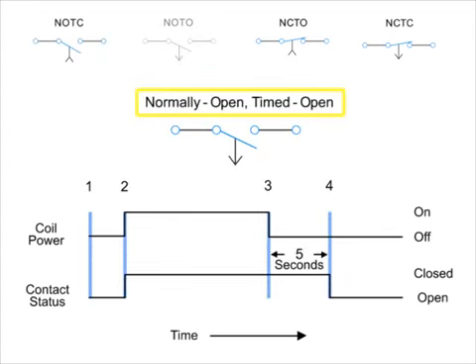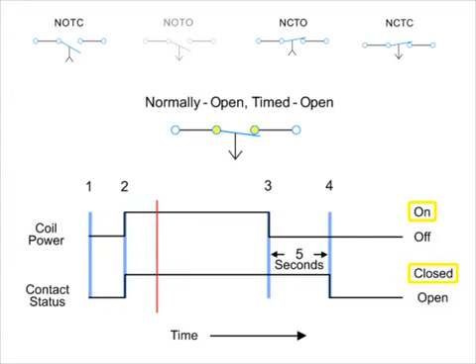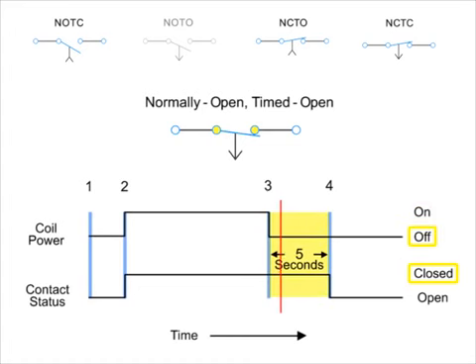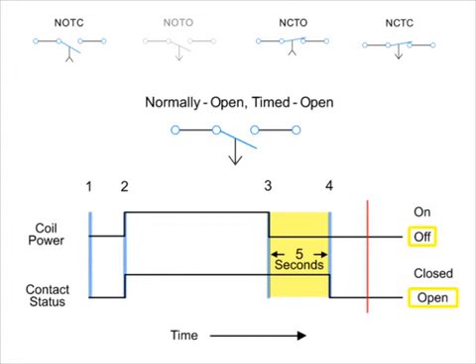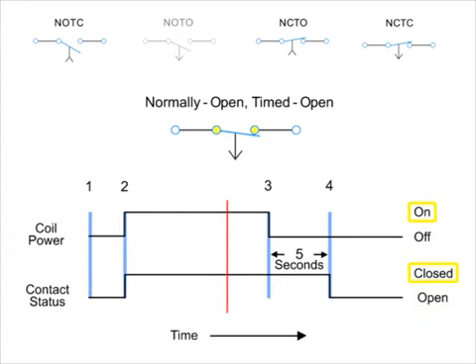Next, we have the normally open, timed open contact. Similar to the normally open, timed closed contact, this type of contact is normally open when the coil is unpowered or de-energized, and closed by the application of power to the relay coil. However, unlike the NOTC contact, the timing action occurs after the coil is de-energized for five seconds.